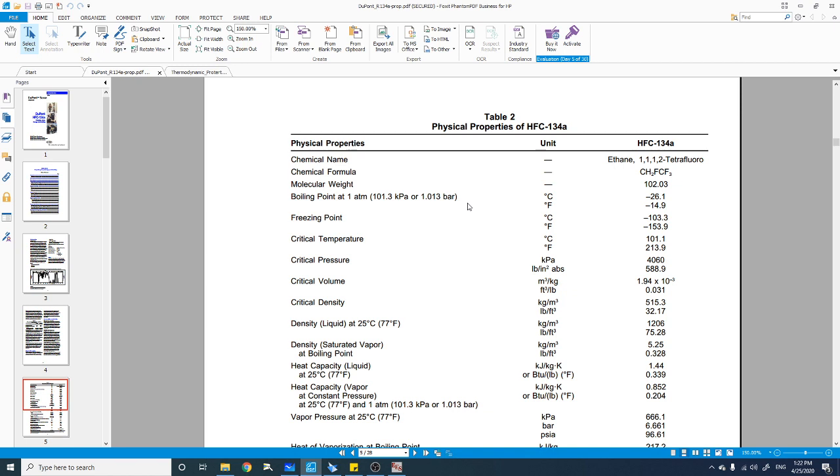So you have a good understanding from this data that if R134a is supplied in a bottle to a ship, it is liquid at saturated conditions at the atmospheric temperature, but at a very high pressure. So the moment you open the valve, the refrigerant escapes from that high pressure inside the bottle to atmospheric pressure. If you suddenly open a bottle containing liquid R134a, you will immediately notice that there is frosting, and the temperature close to the exit of this valve would be -26.1 degrees centigrade. Because you have reduced the vapor pressure, suddenly the temperature falls. This is the behavior of the substance.